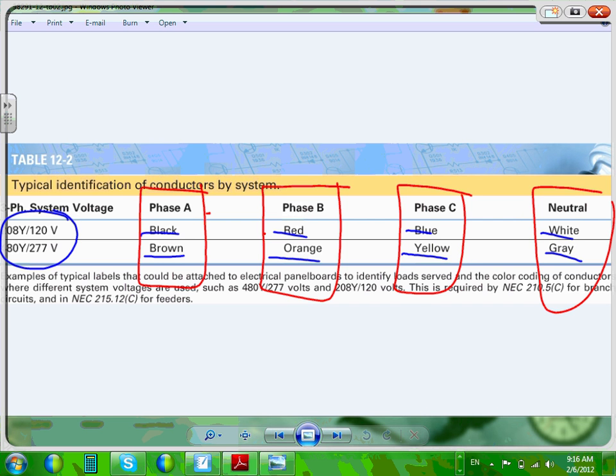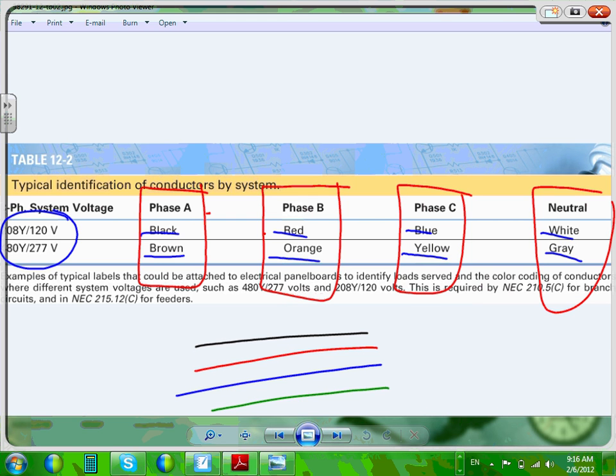Nobody will do that. I mean, it would be stupid to do that. Why? Because the code, it's okay for the code, but nobody will do that. It's a nightmare identifying phase A, B, and C. It's always good to color code them. So what they do most of the time, guys, you have two options: either color coded conductors. So if I'm going to do black, here's my black, and I have a red. And I have a blue, and I have white. I don't have a white, so I'm going to put green for the white. Here's color-coded conductor. That's good enough. Color code them this way.